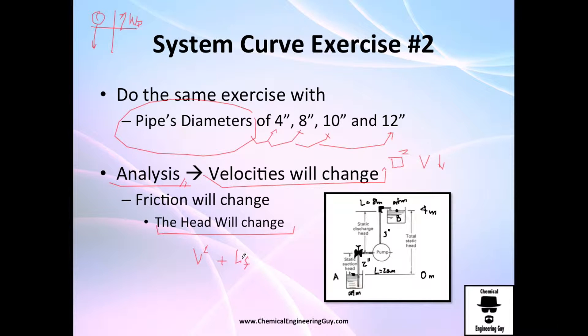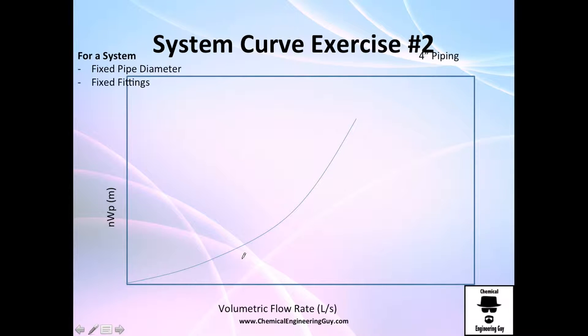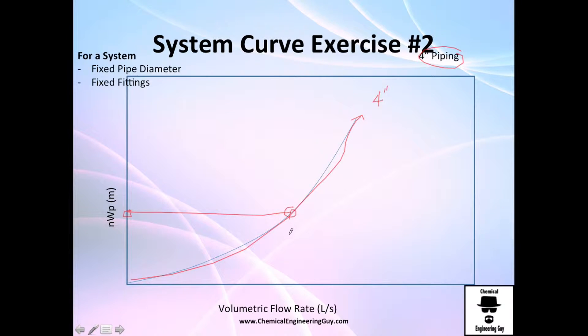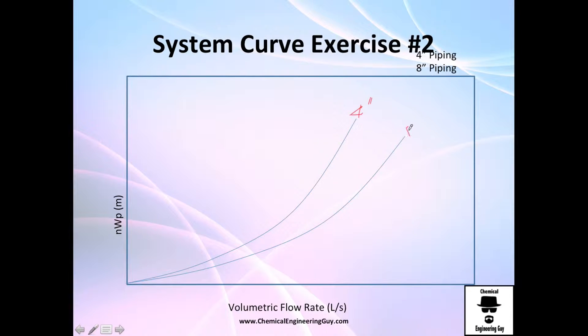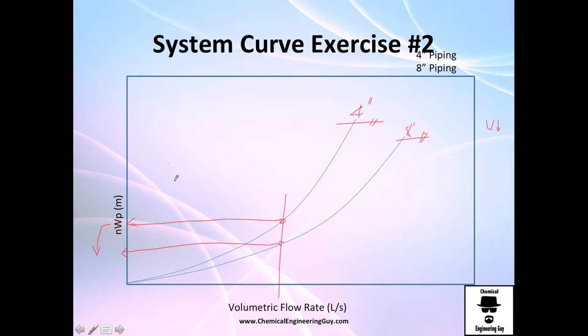We're going to decrease velocity — let's see what will happen. For example, with a four inch pipe, if you increase it to an eight inch pipe, you will decrease the velocities. That means for the same volumetric flow rate, you will have one pump requirement for four inches and another, much lower requirement for eight inches. The pump requirement for the eight inch pipe versus the four inch pipe will be way less, because velocity dropping means friction drop, and friction drop means less energy required.